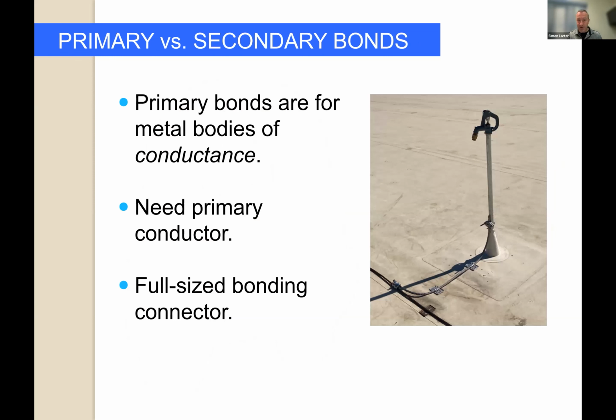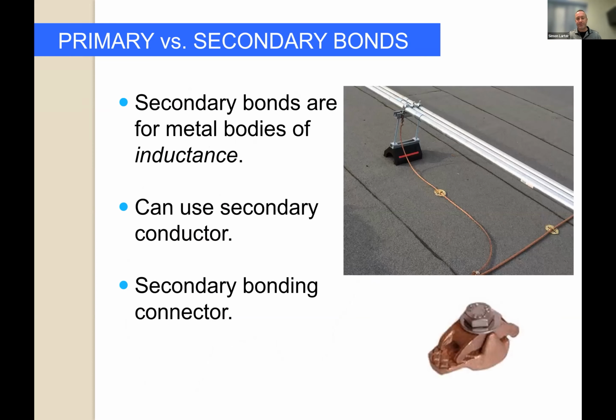Again, primary bonds are for metal bodies of conductance. Conductance, that's again the thing that sticks up outside the zone of protection, is subject to a direct strike, and needs a full-size bond with a primary conductor to carry charge. That's an example, a big warehouse here in Calgary. We bonded that rooftop water pipe. It sticks up high enough, it's thick enough, probably to take a direct strike. That's why we used a main sized conductor to bond it and a main sized bonding fitting.